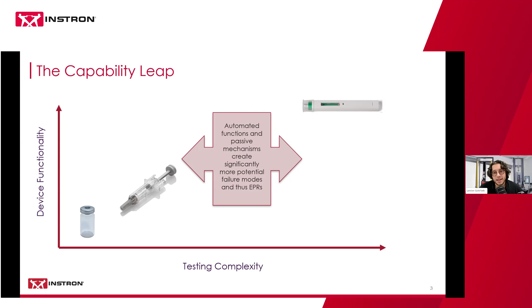And all of these automated functions, all of these new mechanisms of control for the device just mean there's more that can go wrong. There's more ways a device can fail. And simply measuring the total force to use the device is not enough. You need to have a better understanding of how it failed, why it failed, beyond just the quantitative numbers. And those are really all described in what are called EPRs, or essential performance requirements. So we'll talk on the next slide about what all of these essential performance requirements are and what they require of a test system.